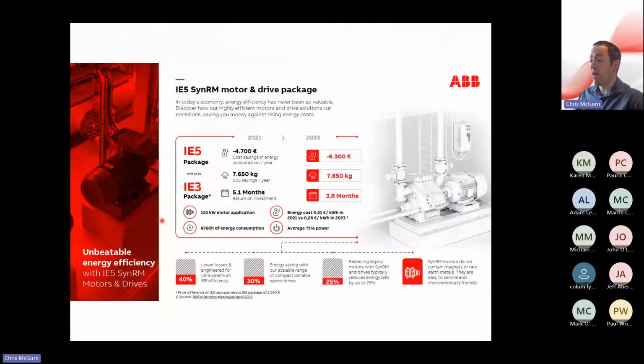This is a typical IE5 SynRM drive and motor package that has been compared over the last few years. In this application, we're looking at a 110 kilowatt motor with a typical operation of 8,700 hours a year at 75% power, and we're looking at energy costs. This shows how the energy cost has changed over the last few years and the potential savings to be made. So in 2021, if you were to buy an IE5 motor against an IE3, you'd be looking at 4,700 euros of savings a year because of the improvement in efficiency between the two. That in turn would give you a 5.1 month return on your investment. So if you buy the IE5, it's going to be more expensive, obviously, but because of the savings in this typical application, in 2021 you would have received your money back in 5 months' time.